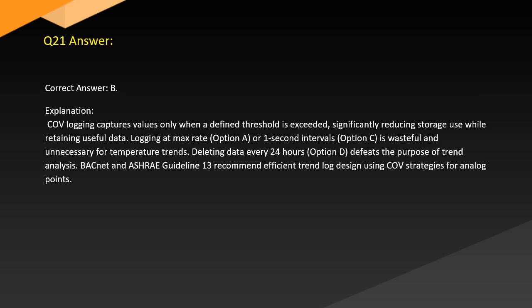Answer. Correct answer: B. Explanation. COV logging captures values only when a defined threshold is exceeded, significantly reducing storage use while retaining useful data. Logging at max rate, option A, or 1-second intervals, option C, is wasteful and unnecessary for temperature trends. Deleting data every 24 hours, option D, defeats the purpose of trend analysis. BACnet and ASHRAE Guideline 13 recommend efficient trend logging using COV strategies for analog points.